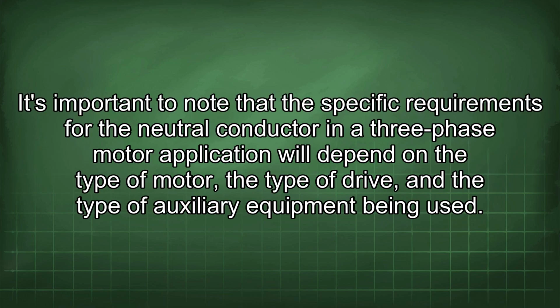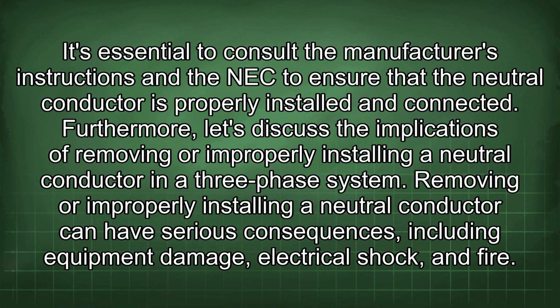It's important to note that the specific requirements for the neutral conductor in a three-phase motor application will depend on the type of motor, the type of drive, and the type of auxiliary equipment being used. It's essential to consult the manufacturer's instructions and the NEC to ensure that the neutral conductor is properly installed and connected. Furthermore, let's discuss the implications of removing or improperly installing a neutral conductor in a three-phase system.